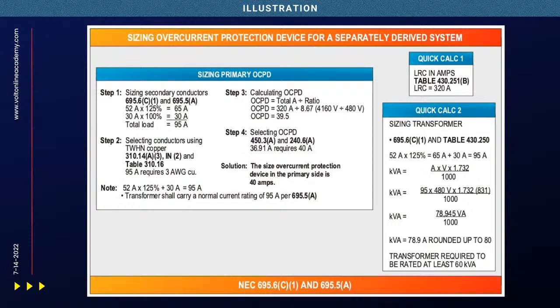Now, if you look at this, we had 52 amps, that was your motor load. That motor has to be taken at 125%, which gives you 65 amps. Then I'm going to add the other loads, which is 30 amps, giving 95 amps of load. So what I'm going to do is determine what the kVA is here.